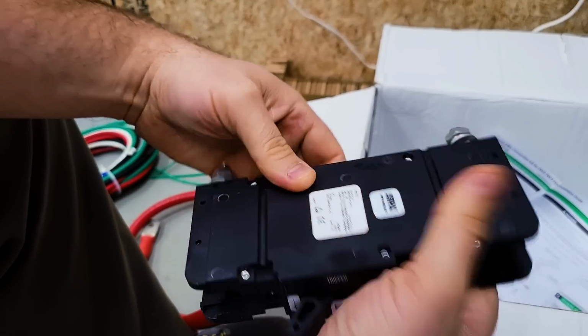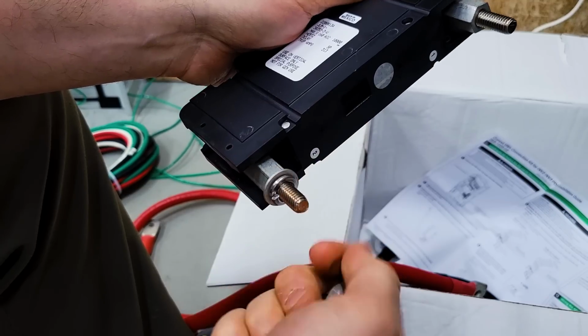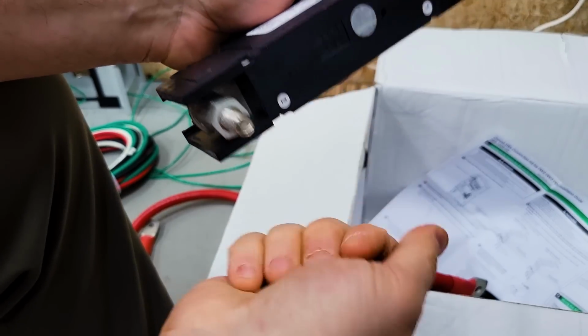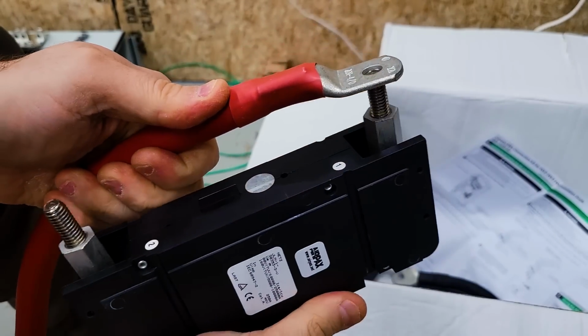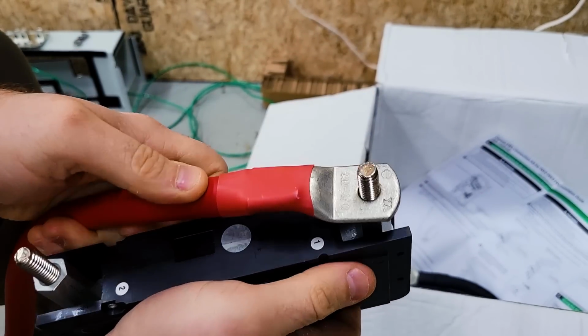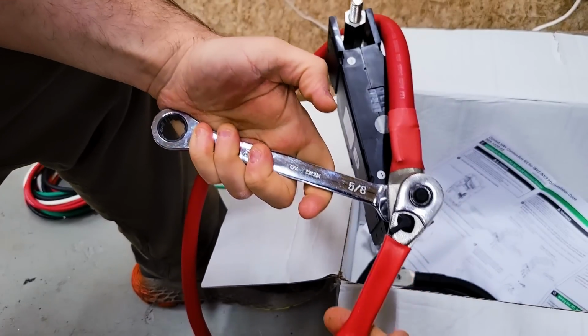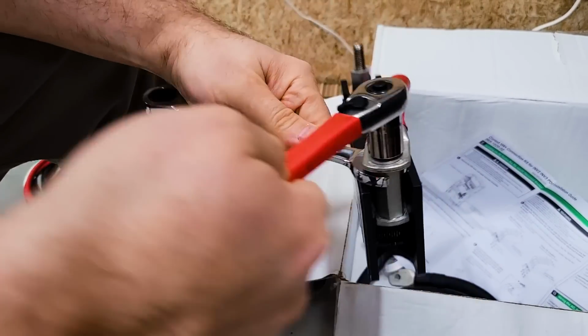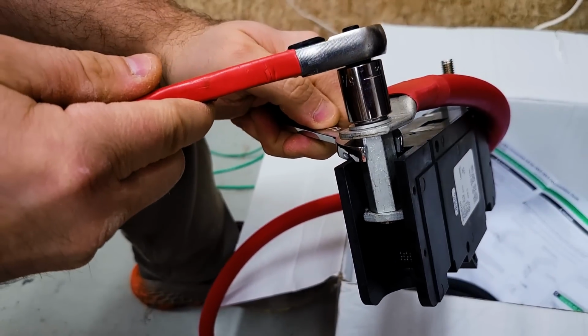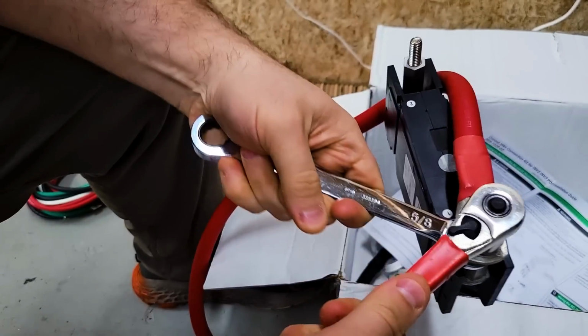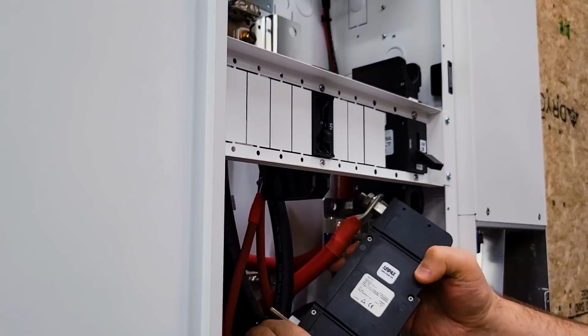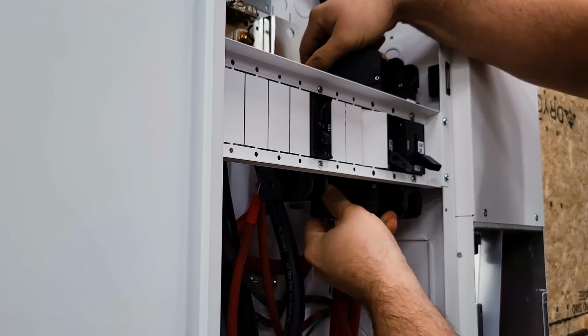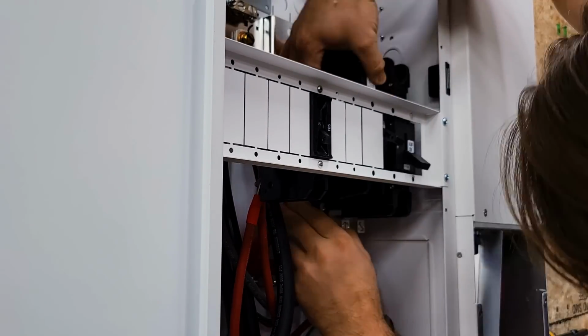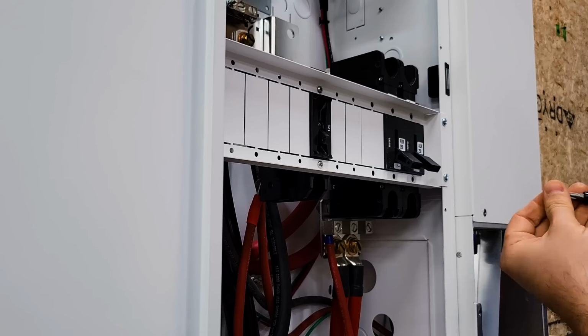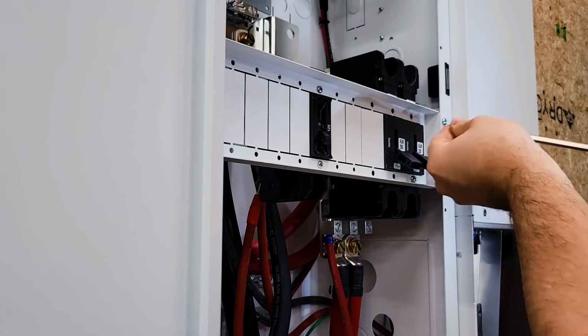So it came with 4-aught wire. Now remember, this is a 6.8 kilowatt inverter. A lot of times when you look at 6.8 kilowatt inverters, they're going to suggest something smaller, maybe a 1-aught or a 2-aught wire. But in this case, Schneider knows that the surge capacity on this is so great, we're talking 12 kilowatts per inverter, that they don't cheap out. They give you really good 4-aught wire to go from the bus bar to the inverter. So that's really nice on their part.